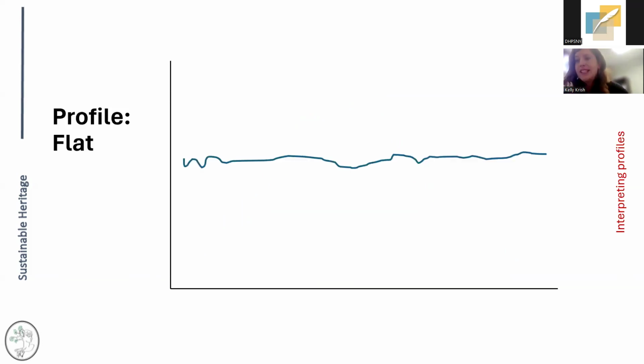On the exact opposite end, some of you might see in your spaces a very flat dew point graph. So this would be within your building, and it's just pretty much flat across. Exact opposite of what we saw with the curved one, both visually and in terms of implication. So this means that you've set very tight preservation standards, which may or may not be necessary for the collection, but it's tight, it's being maintained. And because it's so different from what's likely occurring outside, it's probably quite a large energy cost. So those are kind of the two extremes in terms of how a dew point graph can look from inside of a building.